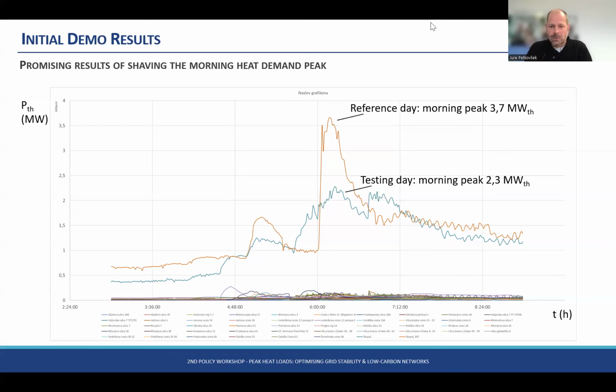The next day we implemented our demand response controller, using a very simple and quite non-invasive solution. Instead of opening the valves within 1 minute at 6 a.m., we extended this period over 1 hour, starting at 5:30 and ending at 6:30. So there was absolutely no impact on the end users' comfort. No building was switched off, and we already achieved quite promising results with such a simple solution.